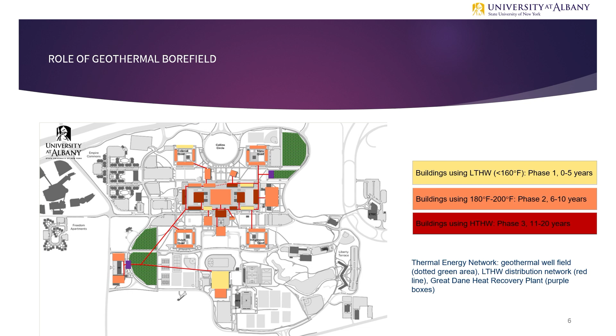We're coming at this campus-wide, central plant level decarbonization project from a place of success. We already have two buildings fully electrified. One is Liberty Terrace, a 500-bed apartment-style residential unit open since 2012. We have 12 years of data from this building, which uses a geothermal-based heat pump system for 100% of its heating and cooling with no backup fossil fuel on site.